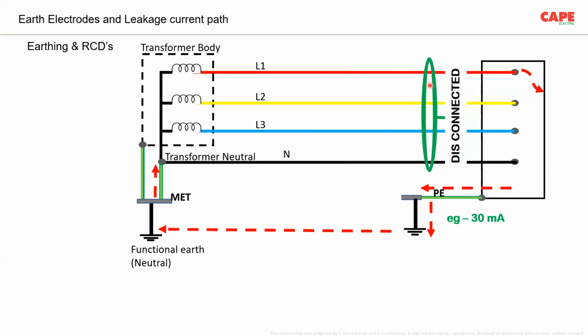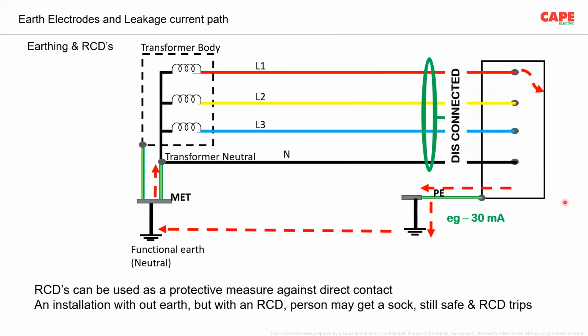Now, the difference between an ELCB and an RCCB, you must understand that. Imagine in an RCCB there is no earthing. The RCCB will not trip. The body of this panel board will be live. As soon as the person touches, since the current starts flowing through the body of the person, immediately the RCCB will trip. So from this, what you should understand is, if you are using an ELCB, proper connection to the earth electrode, and the earth electrode itself, is important in order to ensure disconnection of the supply. Whereas in case of an RCCB, even if the earth electrode or the earth connection is not at all available, the person will get a shock and the MCB trips, or the RCD trips.